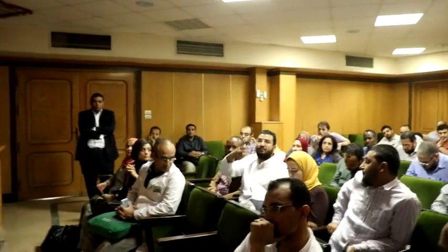We always see a change in the sensitivity after implanting the pacemaker and interrogating the pacemaker. It's always different. If you use this, you should see very, very little difference. Very little difference, like less than 1 millivolt.